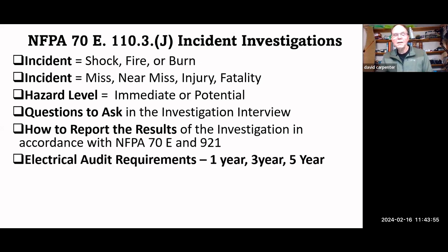The electrical audits are required one every year for the workers and what's actually going on in the field. It's called a field electrical audit. It is required every year. The electrical safety program is required to be audited every 3 years, and every 5 years you have to do what's called an arc flash analysis, or the new term for that is energy incident analysis. That has to be done every 5 years. That's part of what we do.